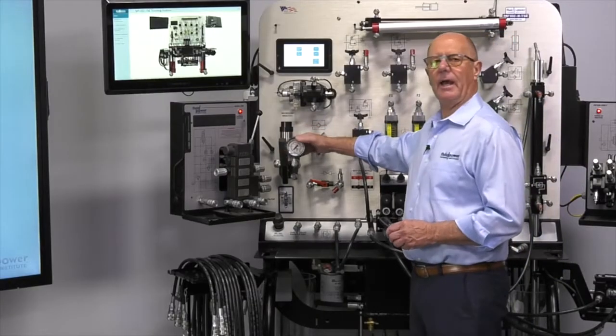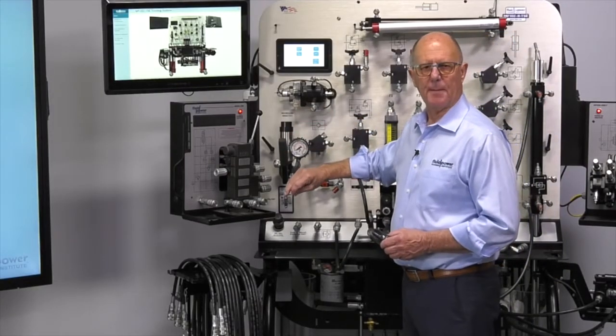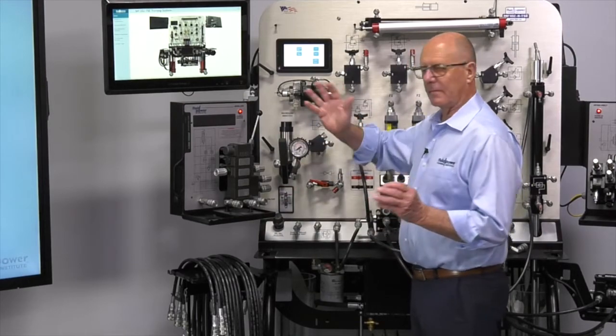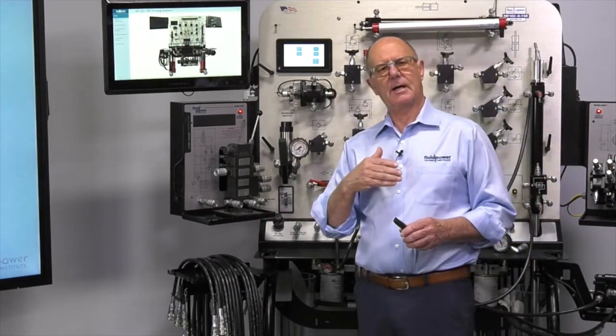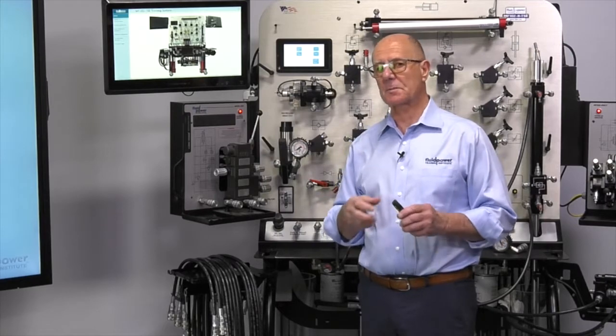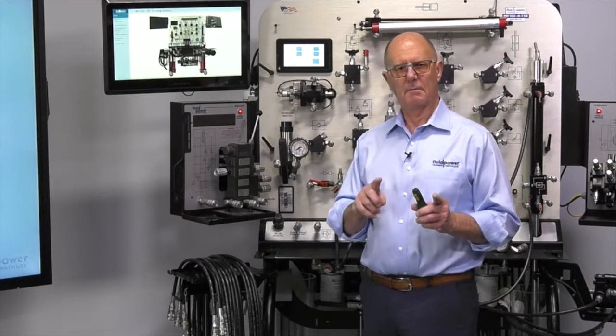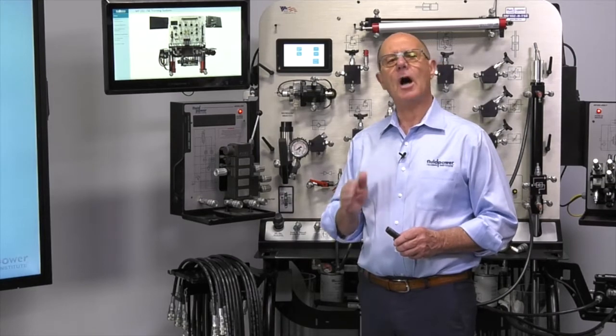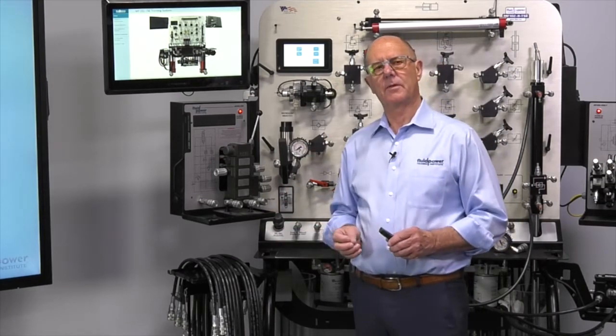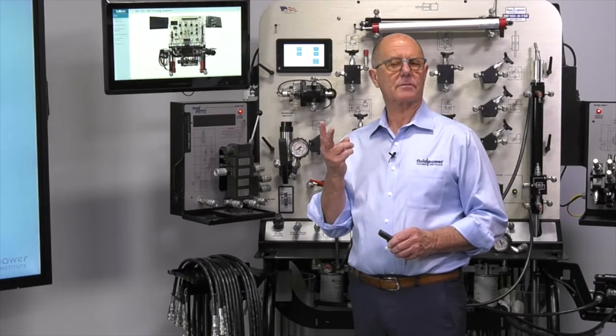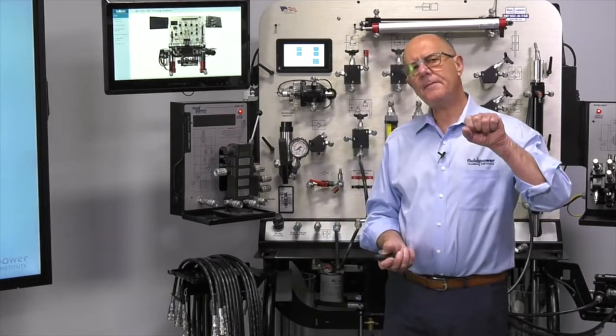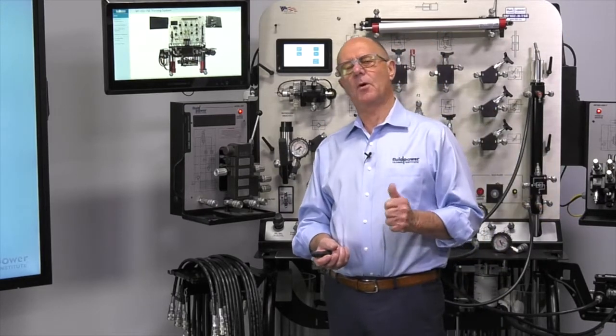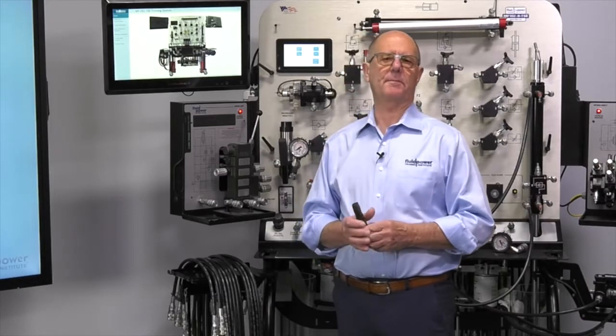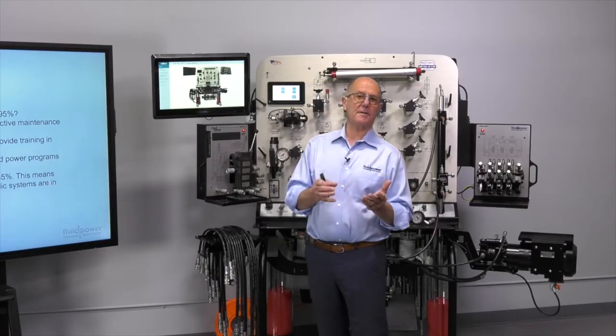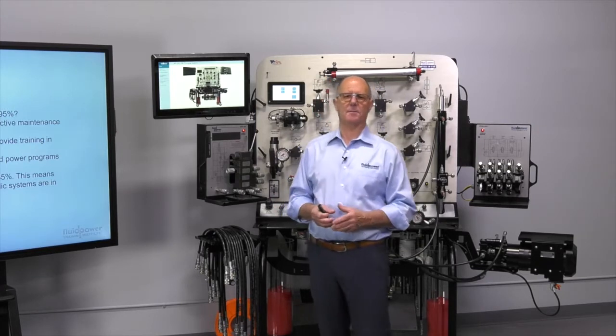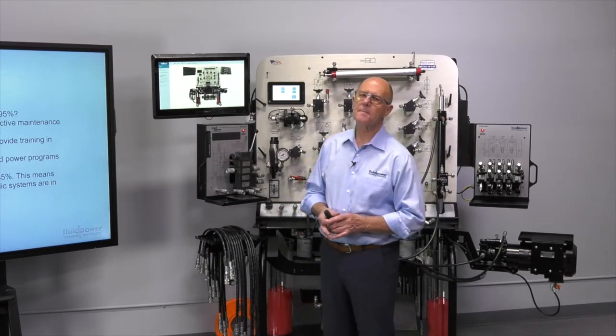On the simulator, we have a microleak test pump. Before I move forward, let's understand that a microleak test pump is specifically designed for the purpose of microleak testing. Do not substitute this pump with a porta power, for two reasons. One, a single push of the handle on a porta power will put you at 10,000 psi. What if you're testing a 1,500 psi rated valve with a 10,000 psi pump? Somebody's going to get hurt.